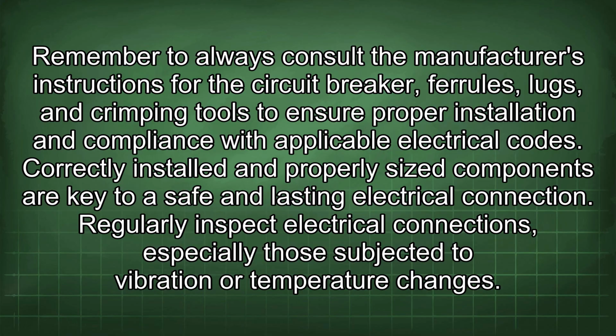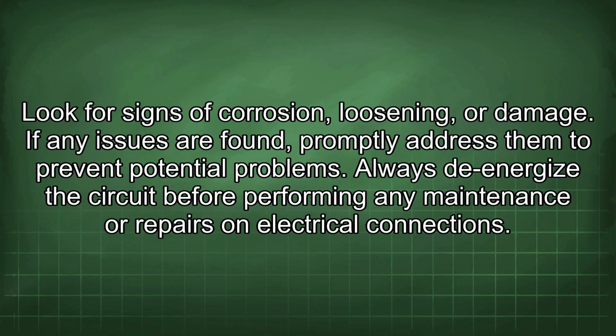Regularly inspect electrical connections, especially those subjected to vibration or temperature changes. Look for signs of corrosion, loosening, or damage. If any issues are found, promptly address them to prevent potential problems.